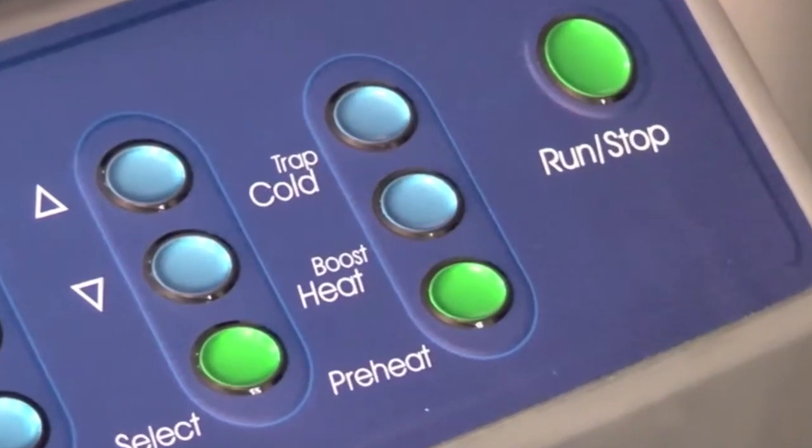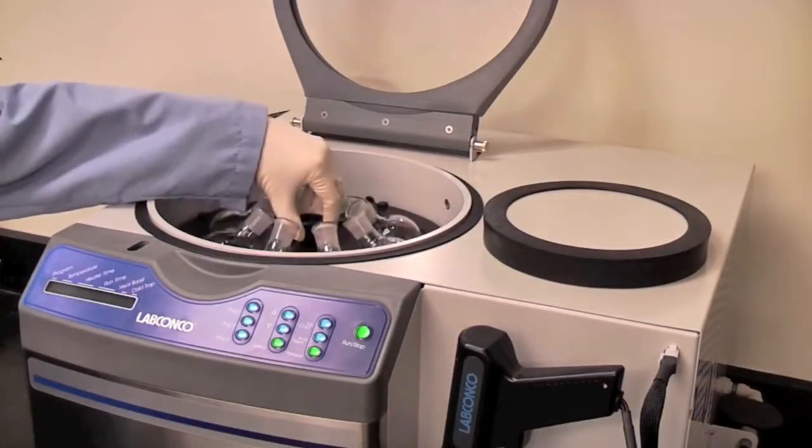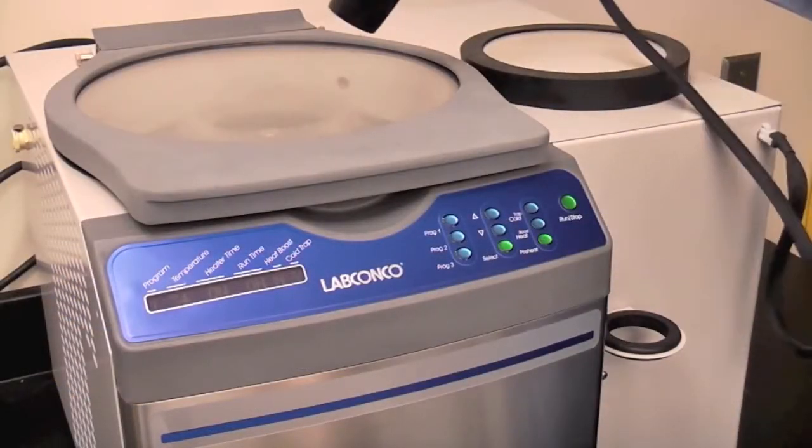For acidic samples, an acid-resistant model is available. A heat boost option is recommended for high boiling point solvents. The CentriVap strobe light saves time by allowing the user to easily see into the chamber to view samples while the rotor is spinning.